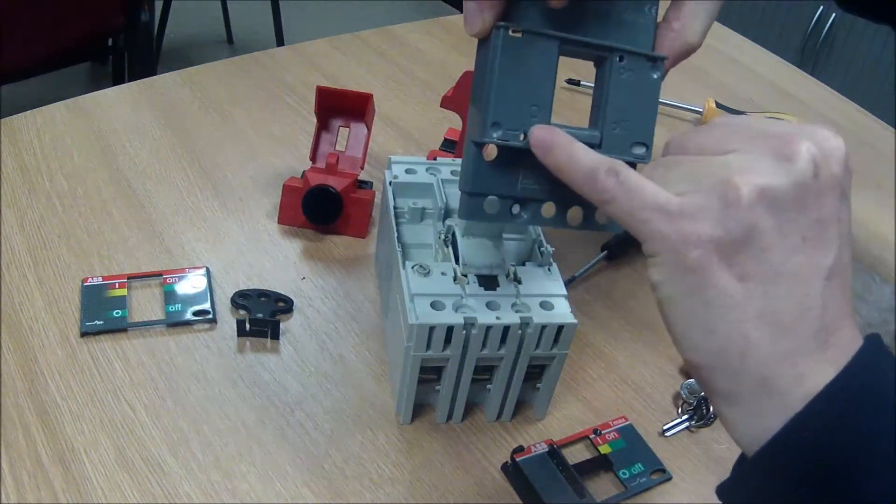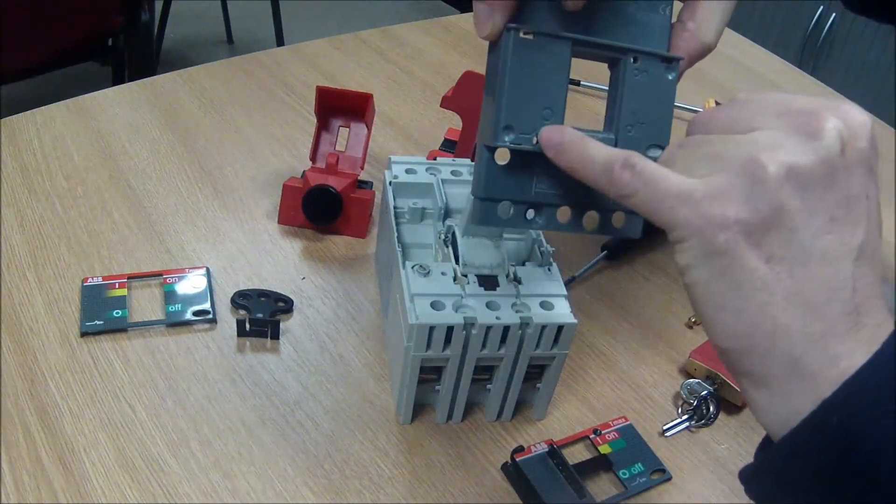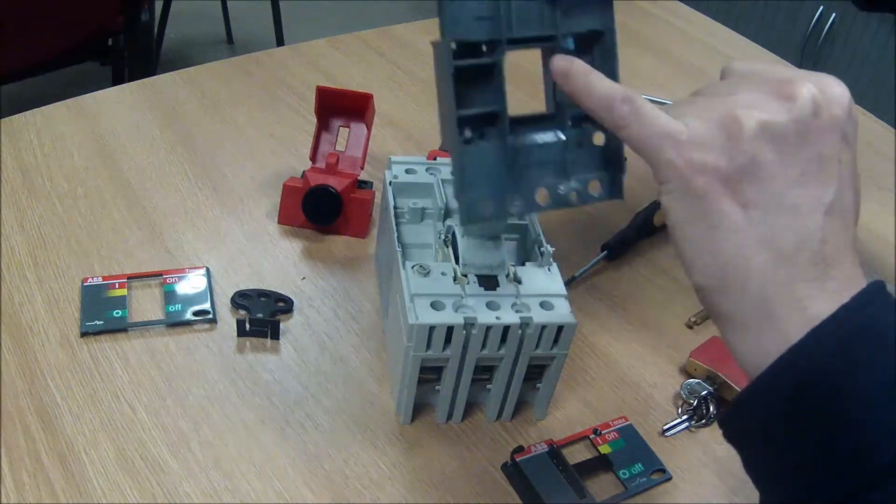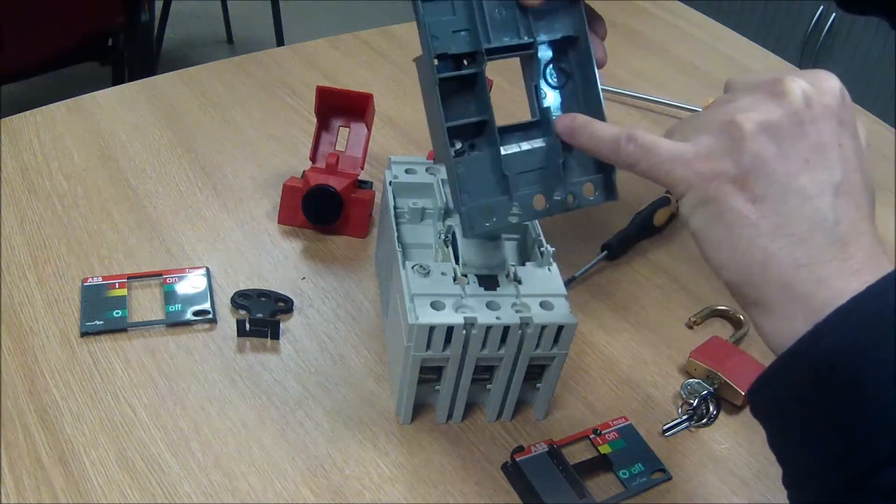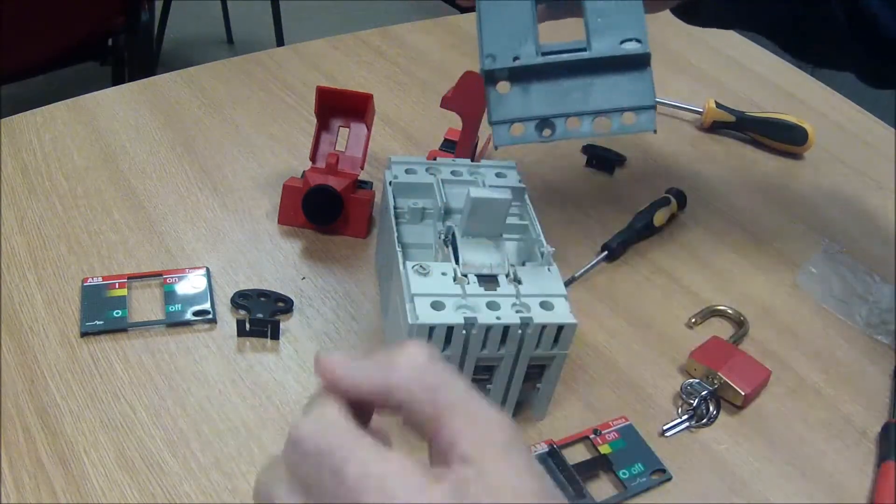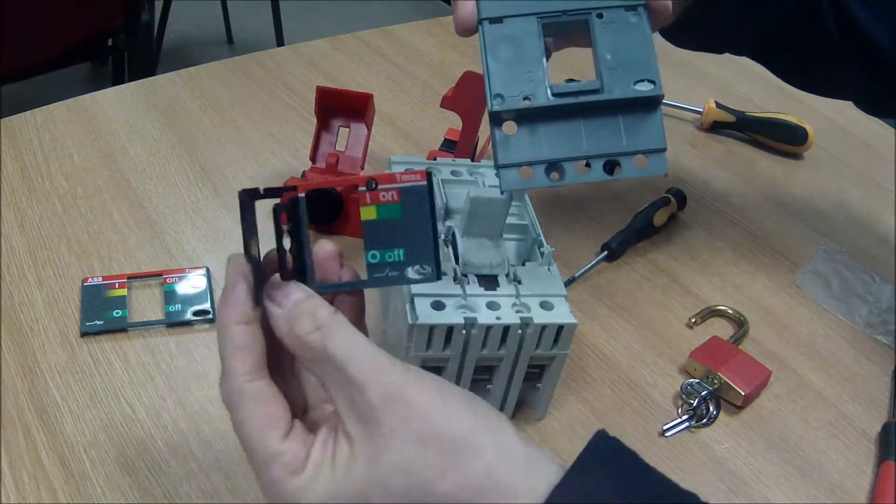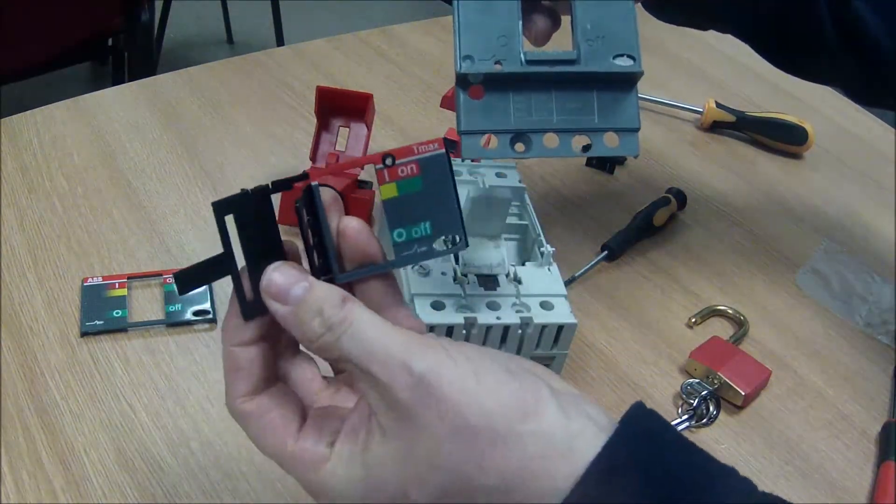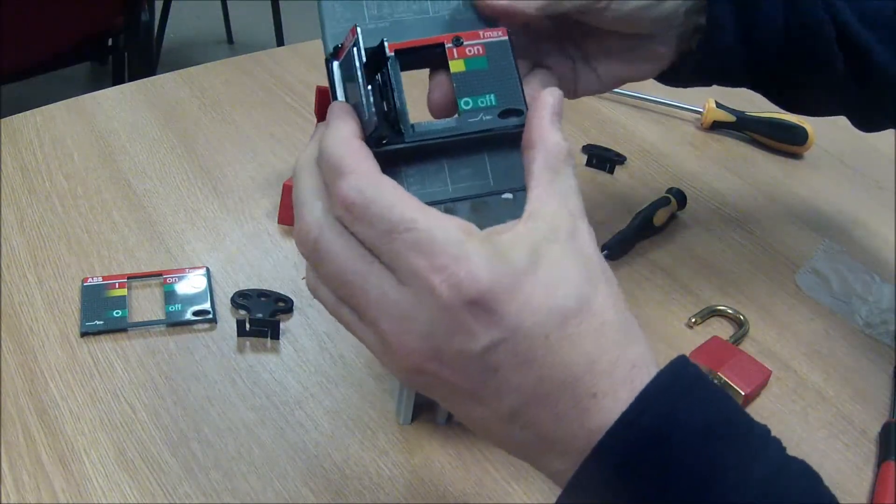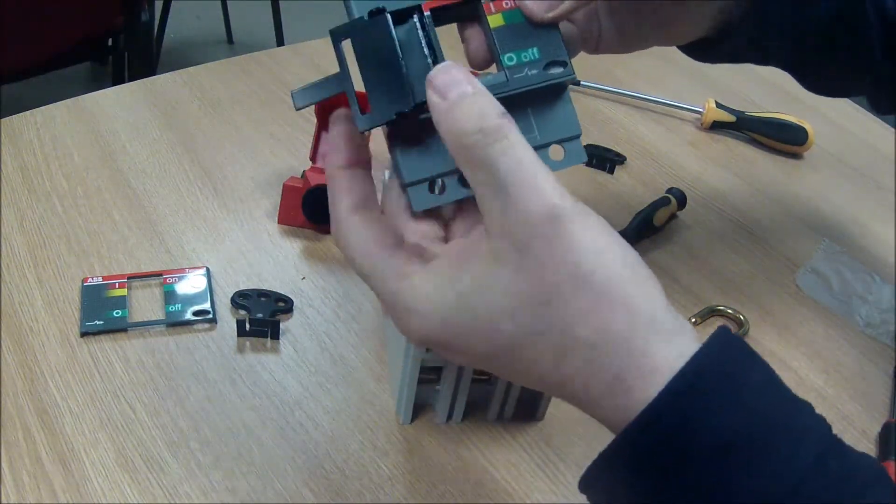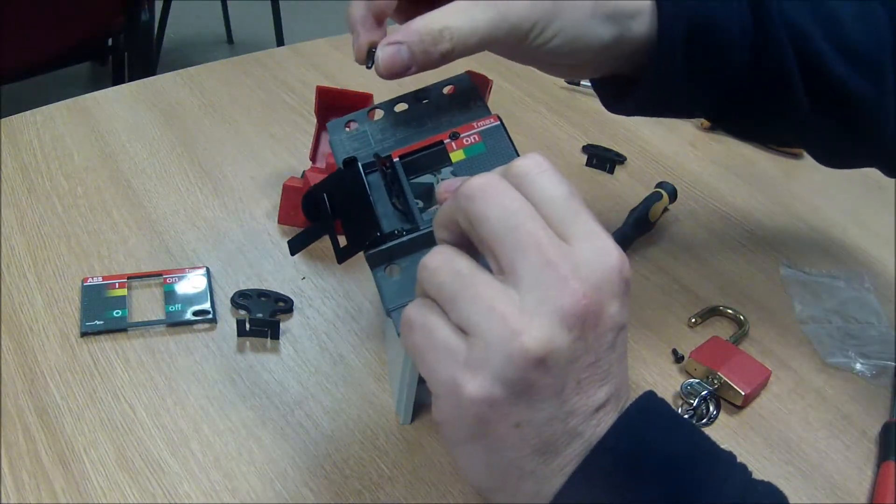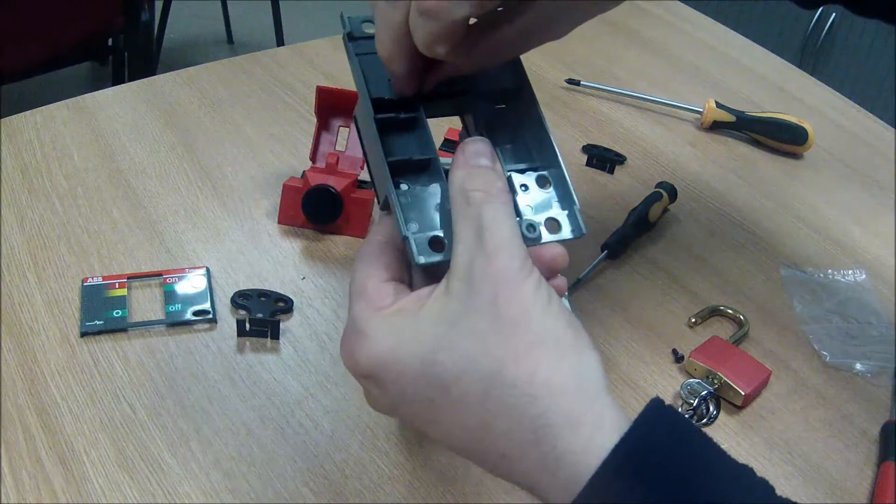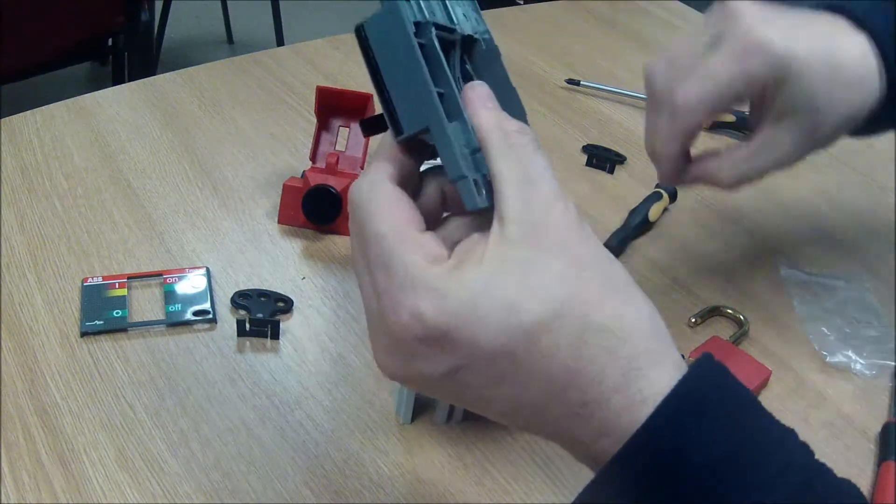And you can see these two holes here. Now those aren't normally there. You have to either punch them through from the back or what I did here was I actually drilled those out. So this replacement component here, the lockout device, fits over the front like that. And in the pack come these two small threaded screws and you insert those from the back and tighten those up.